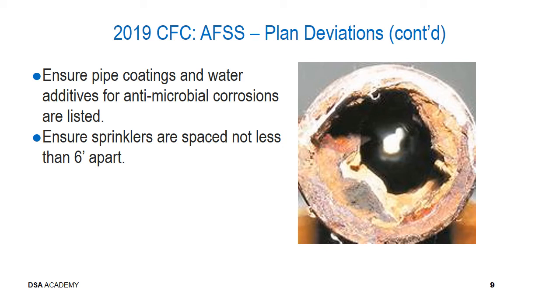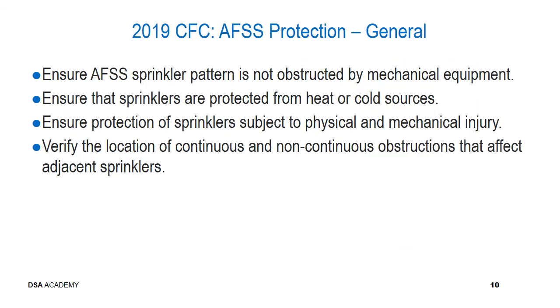Ensure that pipe coatings and water additives for antimicrobiological corrosions are listed. Ensure the sprinklers are spaced not less than 6 feet apart. Ensure sprinkler spray patterns are not obstructed by mechanical equipment. That the sprinklers are protected from heat or cold sources, such as HVAC diffusers blowing directly on the sprinklers, or those sprinklers proximal to refrigeration units. Ensure protection of sprinklers subject to physical and mechanical injury, and verify the location of continuous and non-continuous obstructions that affect the adjacent sprinklers.